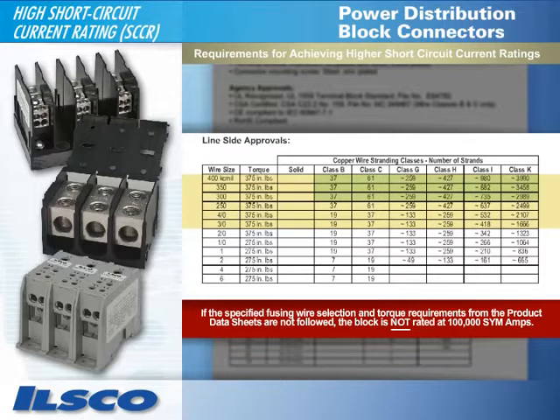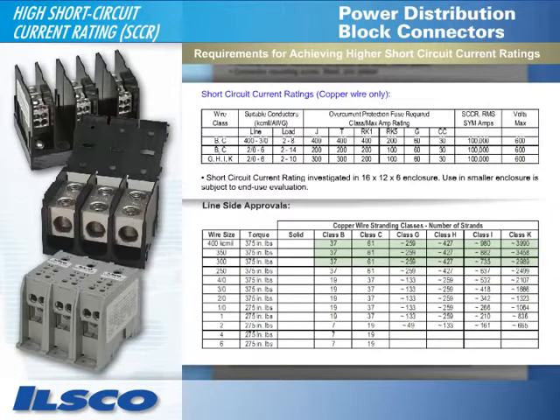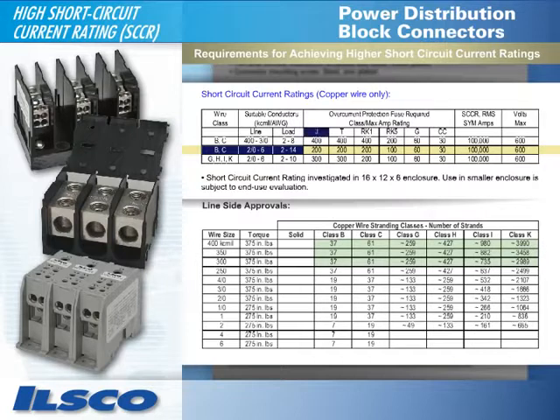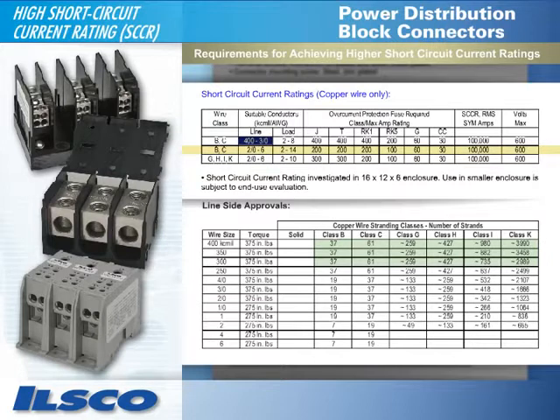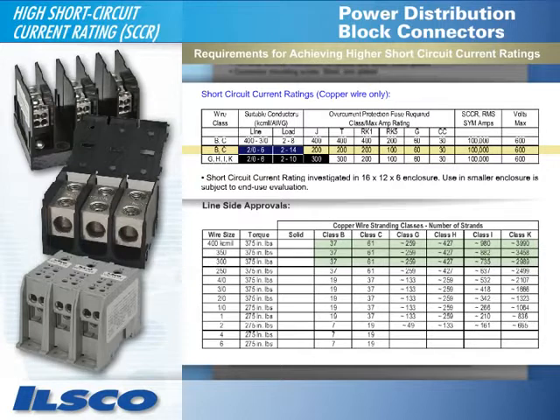Let's look at another example. On line 2 of the same chart, the wire conductor classes are B or C. The suitable conductors for line are 2-0 to 6; load is 2 to 14. For class J fuse ratings, it's 200 amps. This combination of components can be rated at 100,000 SYM amps. Conversely, you cannot use a 400 line wire and a number 10 load wire. You also cannot use a line conductor of 2-0 to 6 and a load conductor of 10 with a 300 amp class J fuse and still achieve a 100,000 SIM amp rating.